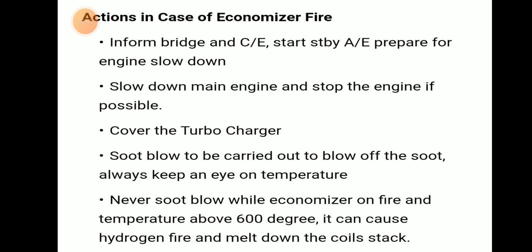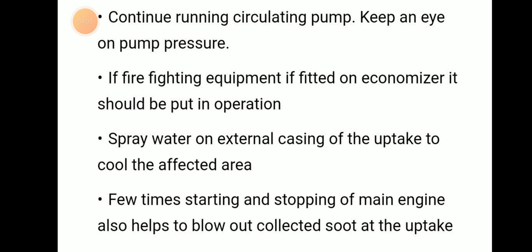If soot blow is performed when the economizer is on fire and the temperature is above 600 degrees Celsius, it can cause hydrogen fire and meltdown of the coil stacks — even the metal will get burned. So we have to be very careful.